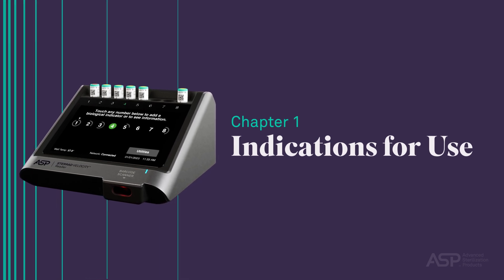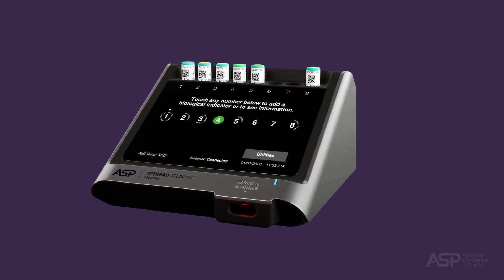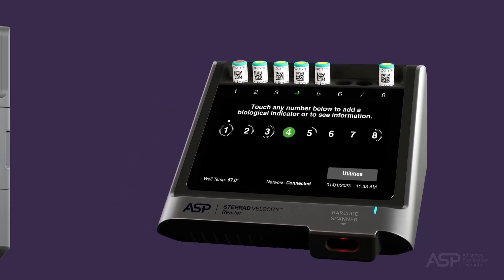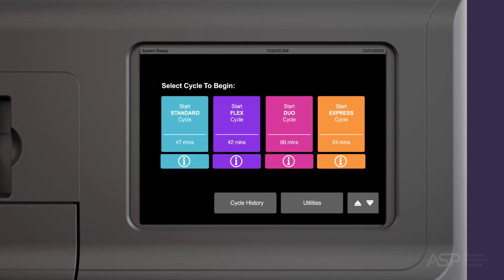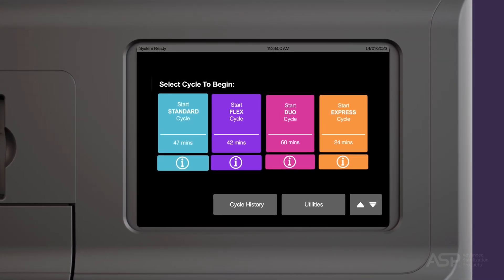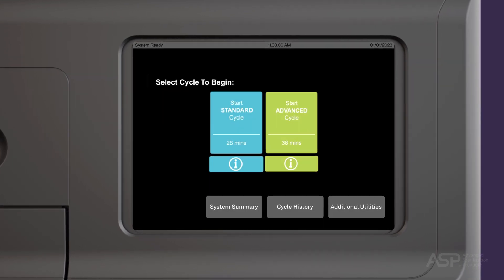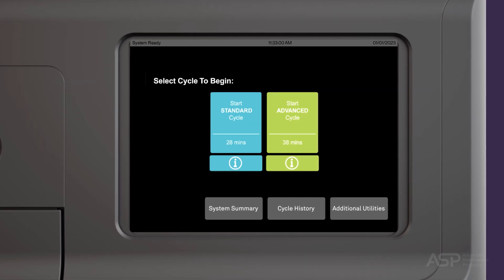Indications for Use. It's important to identify the indications for use of the STERRAD Velocity Biological Indicator in conjunction with the STERRAD Velocity Reader. Biological monitoring provides the only direct measure of lethality of a sterilization cycle. It is to be used as a standard method for monitoring the standard, flex, express, and duo cycles of the STERRAD 100 NX system with and without All-Clear technology, the standard and advanced cycles of the STERRAD NX system with and without All-Clear technology, and the STERRAD 100S system.